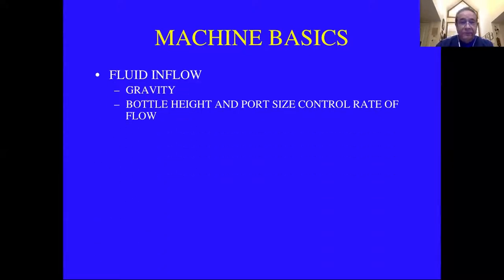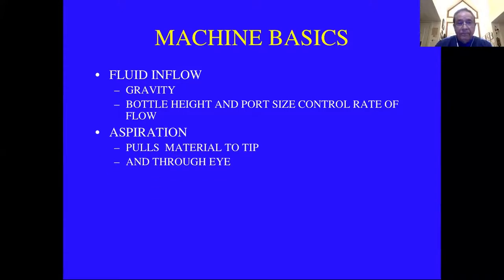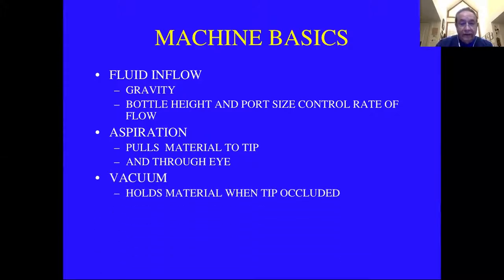The basics of the machine are pretty simple. You have fluid inflow — a bottle, usually with balanced salt solution. Most machines use gravity flow so that the bottle height and port size control the rate of flow when the valve is open. You have an aspiration pump which pulls material to the tip in the eye and then pulls emulsified material out into a disposal bag. Vacuum is generated when the tip is occluded — once occluded and vacuum builds, it helps hold the material on the tip so you can cut.